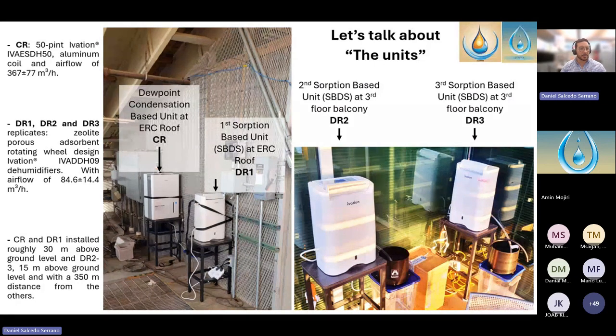I'll elaborate later. And then we have what we call the DR units, which are the zeolite porous adsorbent rotating wheel designed from Ivation. They're dehumidifiers, and it's the same brand, and they suck air, the airflow that they work with is 84.6 cubic meters per hour.